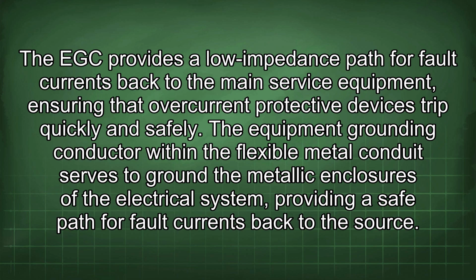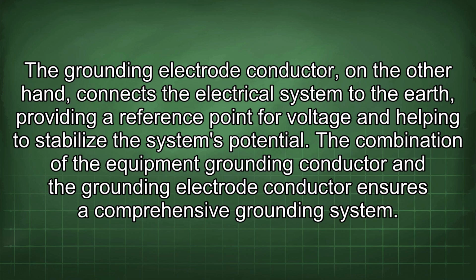The equipment grounding conductor within the flexible metal conduit serves to ground the metallic enclosures of the electrical system, providing a safe path for fault currents back to the source. The grounding electrode conductor, on the other hand, connects the electrical system to the earth, providing a reference point for voltage and helping to stabilize the system's potential. The combination of the equipment grounding conductor and the grounding electrode conductor ensures a comprehensive grounding system.